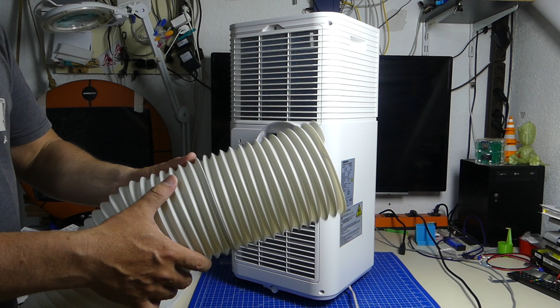One thing I can tell you is people always tell me to use bigger hoses. I'm using the hoses that came with the system right now, and they work out fine. The thing about air is it compresses really well, so when the fan compresses the air to push it out, it doesn't really make a difference how big the hose is to a certain extent. The only problem is on the suction side - that's where a bigger hose makes sense, because it doesn't only compress, but you can also lower the pressure. That means the cooling efficiency goes down. But with these systems, we pull so much air that it doesn't really make much difference if you have one of these hoses or the next size up.